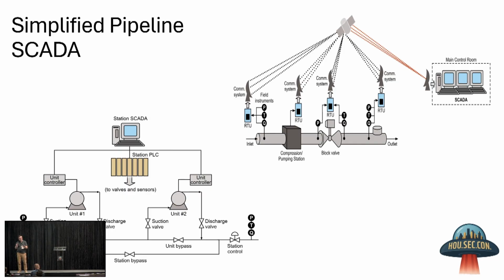You always have a level of trust that needs to be in place because some timing requirements can't deal with the overhead that zero trust would apply. Encrypting this signal may disrupt its ability to maintain the latency I need when communicating high throughput information between a sensor and a controller, or a suite of sensors and the controller. There has to be a level of implicit trust between those two devices.